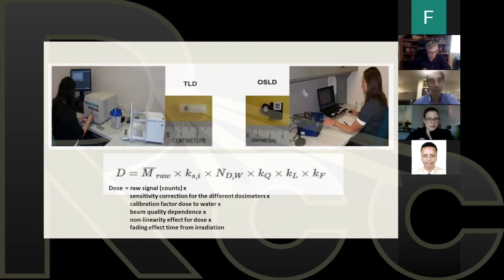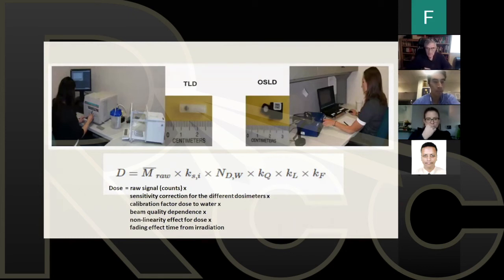Is it better to get the measurement of the output in electrical units and then manually convert it to dose using the calibration and correction factors, or inputting these factors in the electrometer to get radiologic measurements? Well, I'm familiar with the first way because that's what I do. And the second way would work as long as you have confidence in what you're doing, because you're not changing any of the conditions of the radiation, and you've just decided to include it in the electrometer. That's fine as long as you know you're doing it correctly. So either way is fine.